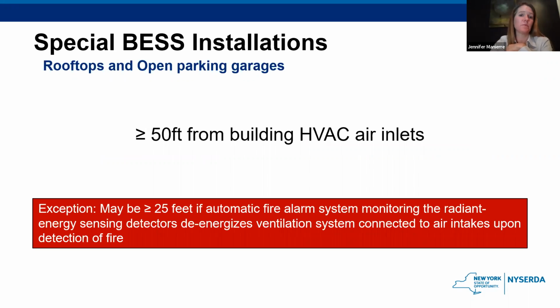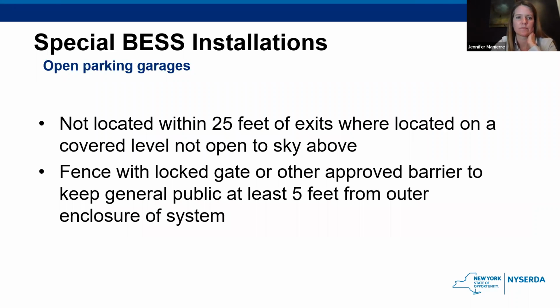For both rooftops and open parking garages, systems need to be at least 50 feet from any of the building HVAC air inlets. There's an exception where if you can have the system set up to automatically de-energize the ventilation system or close the dampers, you can get closer to those air inlets, but otherwise it needs to be at least 50 feet. For open parking garages, the systems cannot be within 25 feet of exits. And there needs to be a fence or some sort of locked gate or other barrier to keep the public at least 5 feet away from the outside of the system.